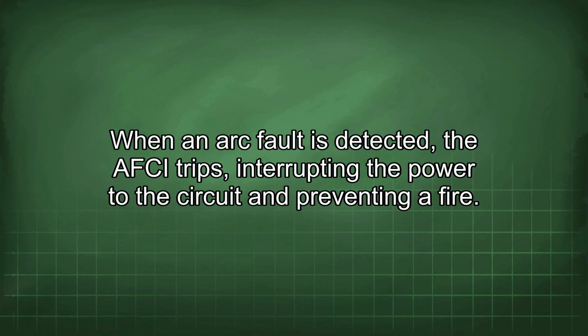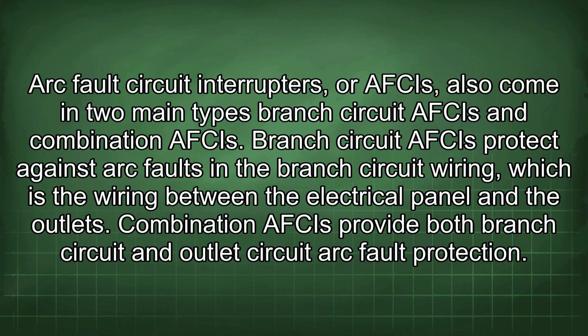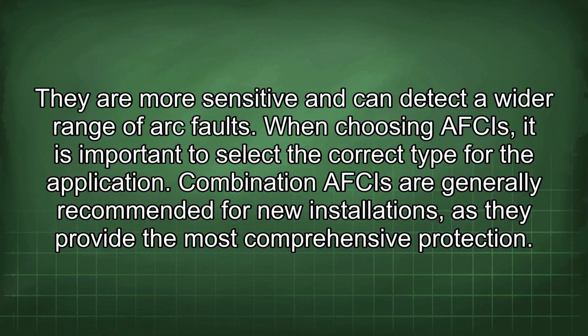preventing a fire. Arc fault circuit interrupters, or AFCIs, also come in two main types: branch circuit AFCIs and combination AFCIs. Branch circuit AFCIs protect against arc faults in the branch circuit wiring, which is the wiring between the electrical panel and the outlets. Combination AFCIs provide both branch circuit and outlet circuit arc fault protection. They are more sensitive and can detect a wider range of arc faults.